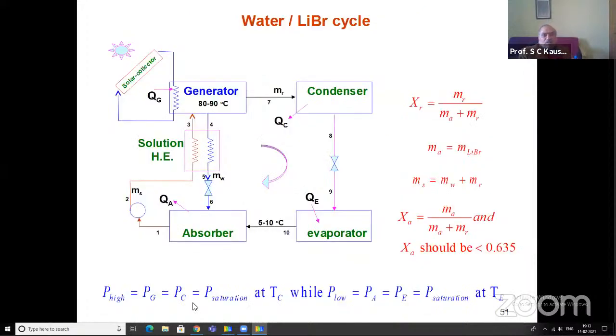Now for water lithium bromide, what is needed is how to thermally design this system. For solar operation, the solar collector is supplying heat to the generator in the range 80 to 90 degrees centigrade, and the evaporator is operated at 5 to 10 degrees centigrade. The condenser and the absorber are operated from 30 to 40 degrees centigrade. And we have two pressure levels, the high side pressure in the condenser and the generator, and the low side pressure in the absorber and the evaporator.